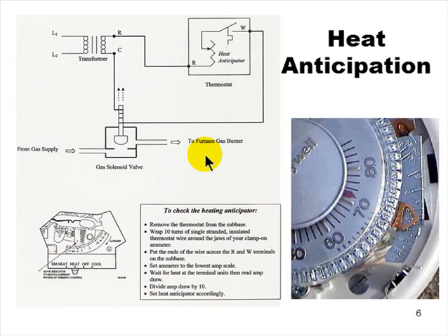When it comes to heat pump thermostats, it's really important that you get the manufacturer's information. When you're going to replace a thermostat on a unit you're not familiar with, I'm making up a name here, say it's a York unit, and you don't work on York, get the model number of the indoor unit and the model and serial number of the outdoor unit. Go to York and say, look, this is what I got. What thermostat do I need? Don't just go take a generic two-stage heating, one-stage cooling off the shelf. It may not work well.